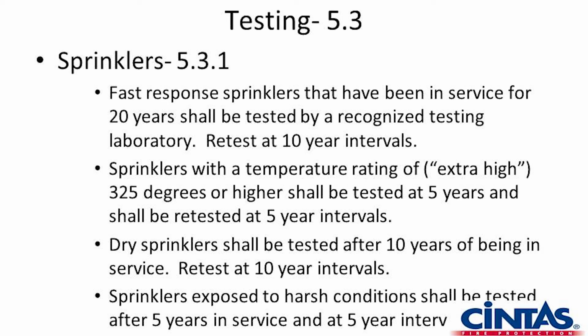If we've got 100 sprinklers, we're not going to say every head has to be replaced. We're going to send you a quotation to remove a sample and have them tested. Let's see what happens if you have a higher fail rate. Once we take that sprinkler out, it's destroyed by UL as they test them because the operating element has been fused. There's no way to put it back together to reuse it, so a new sprinkler is put in its place.